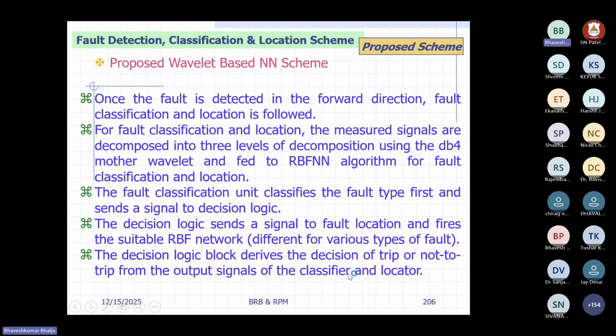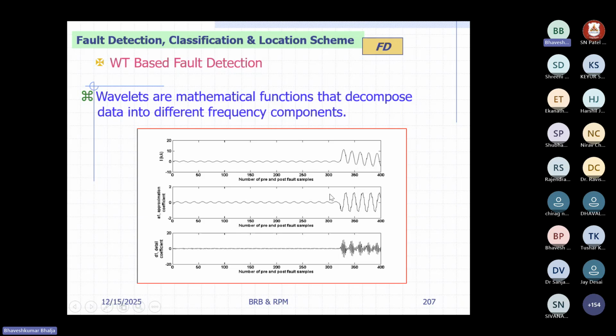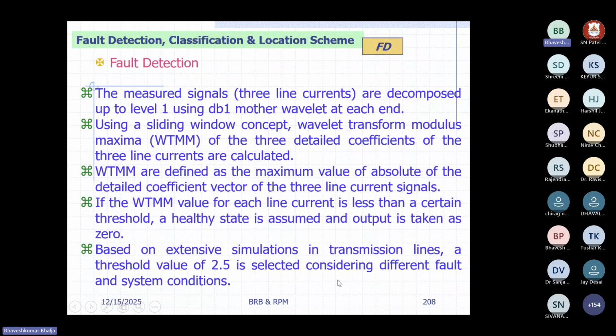Okay. Now, if you look at the waveform, I have used wavelet transform as the feature extraction part. You can see that the first graph is the current magnitude. This is the instant where the fault occurs, and then you have several post-fault cycles. From this instant to this instant is the pre-fault period, and I have calculated some coefficients. You can likewise calculate any type of coefficient depending upon which method you are using. Here I have used two coefficients, A1 and D1, and then I have calculated the wavelet transform maximum modulus.